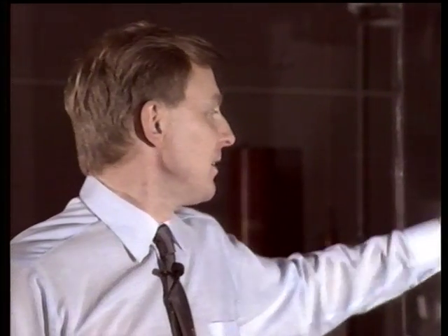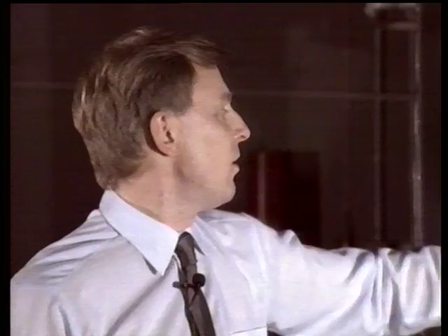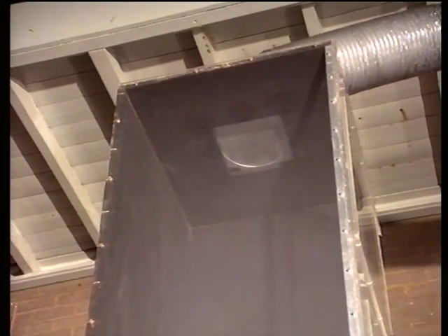On this side, the smoke spreads laterally, but in this case, because we've got an atrium building there, which is opened onto the mall, the gases spread into the building and they rise, causing severe smoke logging within the atrium. Now, the reason for this is that the fire basically is acting as a pump. It's trying to draw air in at low level, and because we've closed it off, it pulls the contaminated air back at low level and back towards the fire.